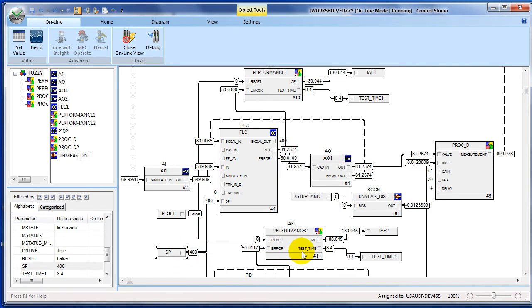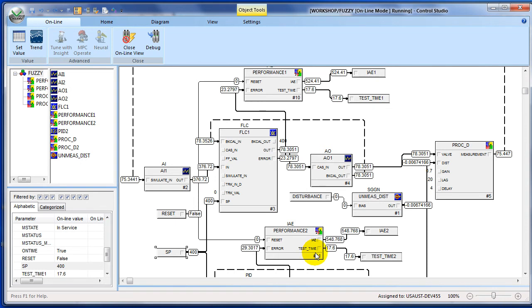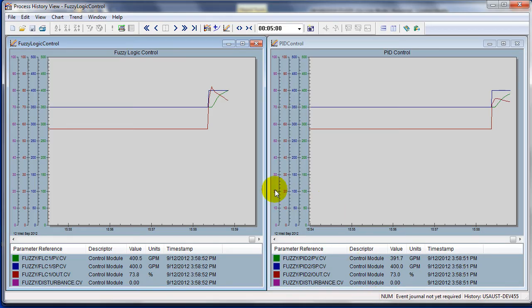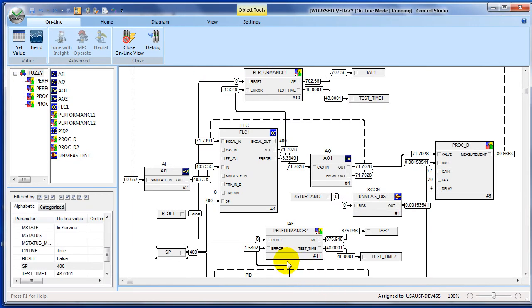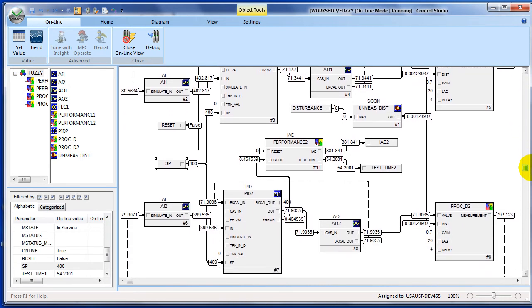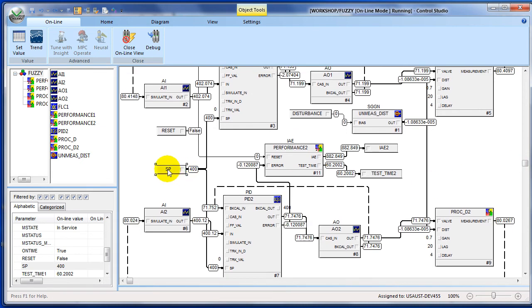As a result of that set point change, we have an error between set point and PV, so our integral of absolute error starts to accumulate. And as we can see immediately, there's some difference between PID and fuzzy — fuzzy having less integral of absolute error than PID for exactly the same change in set point. Looking at the trend, the valve is shown in red, and for fuzzy logic control more aggressive action is being taken due to its nonlinear behavior. This gets us to set point faster.